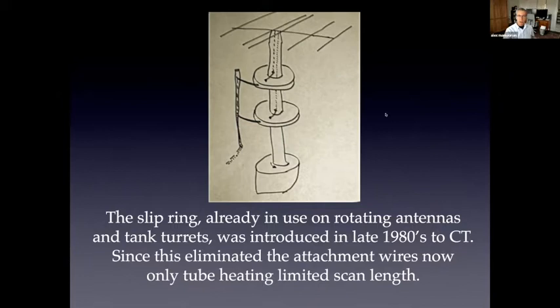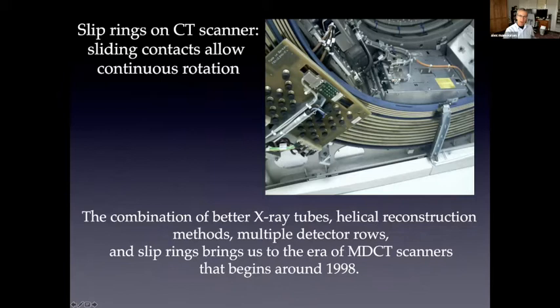So this is what the slip ring looks like on a modern CT scanner. So there are multiple rings and the contacts are in this panel. So you can rotate the tube indefinitely without worrying about wire wrapping. And remember, there's a lot of voltage going through these contacts. So this is a pretty sophisticated electrical and mechanical design.